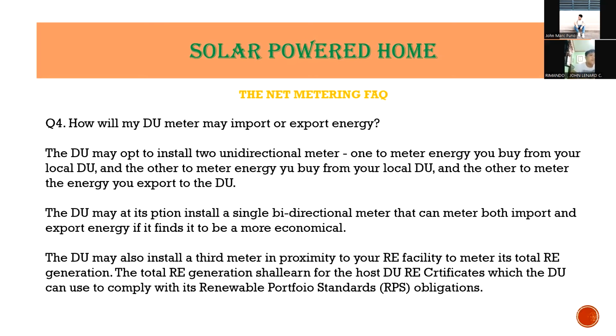How will my DU meter my import or export energy? The DU may opt to install two meters, one to meter energy you buy from your local DU, and the other meter to energy you export to the DU. The DU may instead install a single bidirectional meter that can meter both import and export energy, if it finds it to be more economical. The DU may install a third meter in proximity to your RE facility to meter its total RE generation. The total RE shall earn for the host DU RE certificates which the DU can use to comply with its renewable portfolio standards obligations.